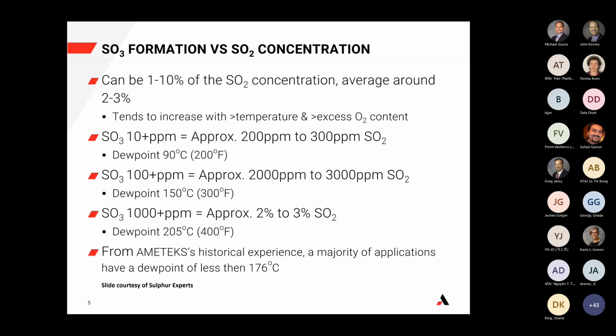Now, most applications will not run that high in an incinerator type application. Typically, in the modern age of, for example, sulfur recovery units, their efficiency will be well above that and produce below 2 to 3% SO2. So what we find from AMETEK's historical perspective is that a majority of the applications typically have a dew point of less than 176 degrees. What this means is that if you look at the wetted system for your CEMS analyzer, typically the first cold point it's going to hit is the probe nozzle, and that's where most of the initial condensation of SO3 ends up happening.